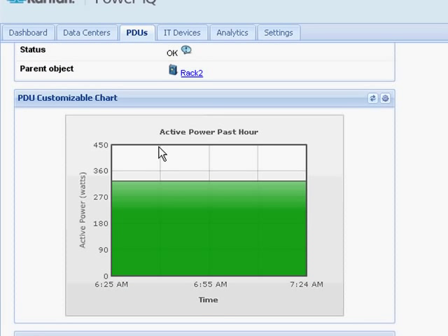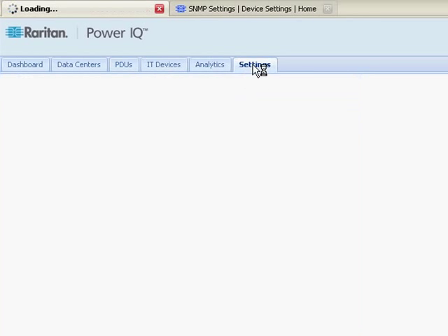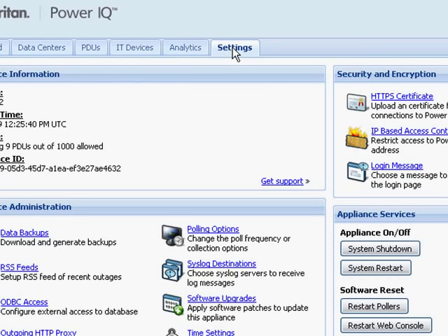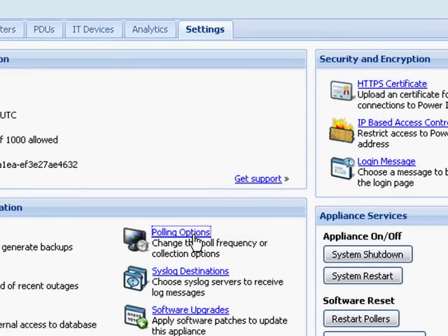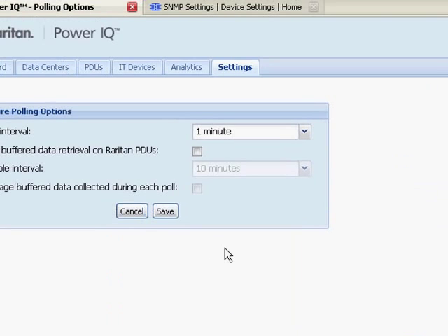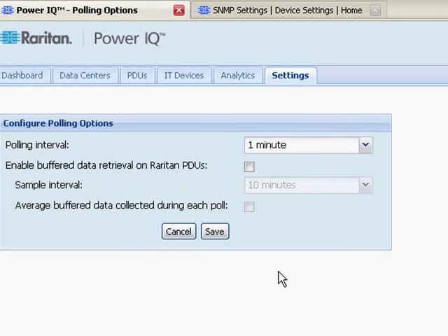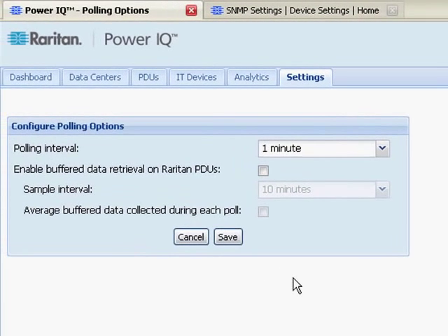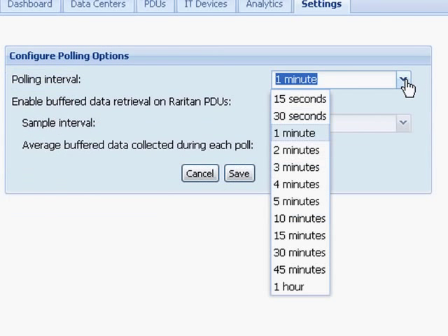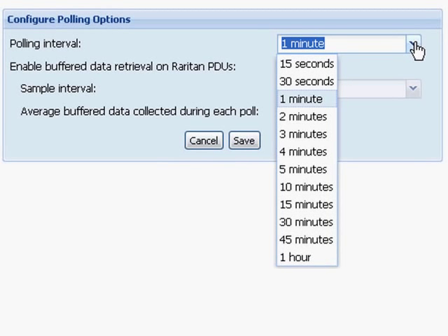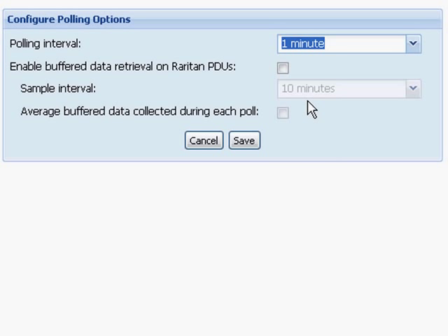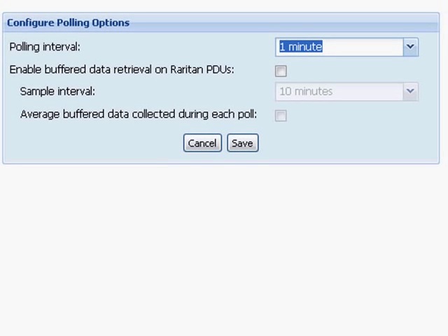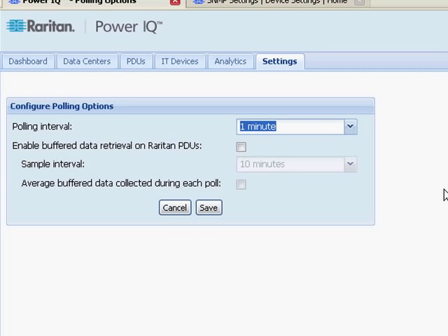If I'm not showing data here, the next thing I would check is on the settings, and I would go to my polling options. Again, under the assumption that you've just installed your PowerIQ, and you want to quickly start to get data into the system, you want to check your polling interval. Since if my polling interval was one hour, I wouldn't get my second data point for probably an hour after I've installed it. So I immediately set the polling interval to something shorter, such as a minute, so I can start to accumulate data and make sure that my analytics is working correctly.